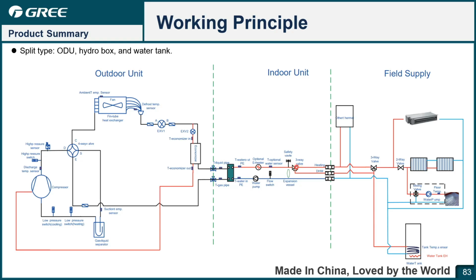If the customer wants the hot water for shower, then this part will open to supply the hot water to the tank and then circulate. If the customer wants the heating, cooling or floor heating, this part will open to supply the water to the FCU or the radiator, and then circulate, flow back. Okay, so that's the water system circulation.